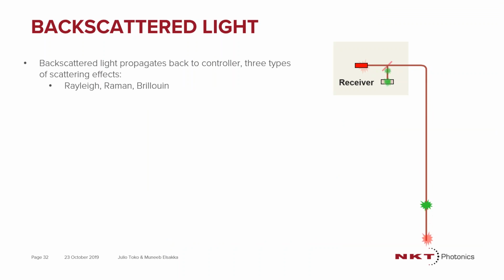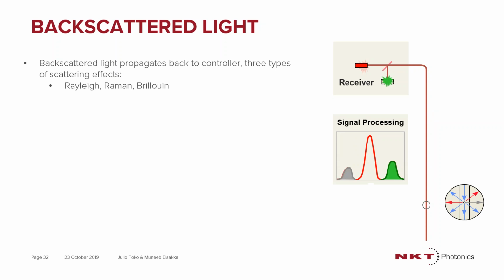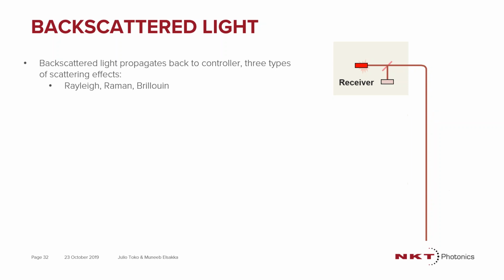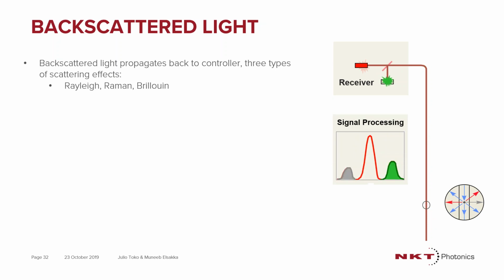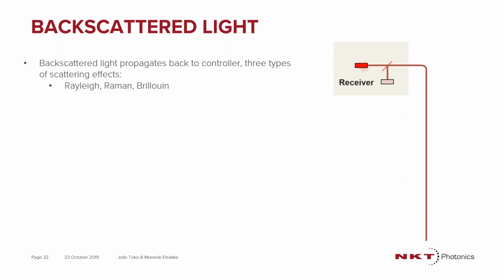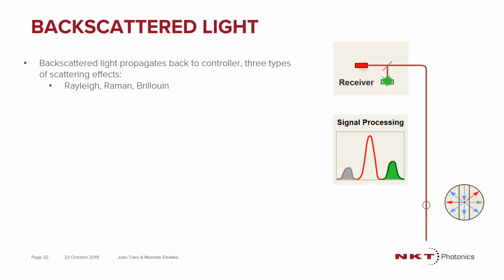Now I'm going to talk a little bit about how the technology works. Essentially, what's going on is the same as in any type of fiber optic linear heat detection. Most of the time, we're using a laser, so you send a laser pulse down the line of the cable. This is a phenomenon that we call Rayleigh backscattering initially, and then the second phenomenon to measure temperature is Raman backscattering. So as the light is traveling through your fiber, here in this case, we're showing a red light going down the pulse, and you automatically get a pulse that goes back towards the receiver or the controller. So this pulse will give you two signals.